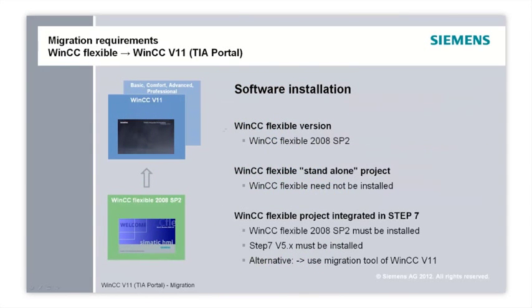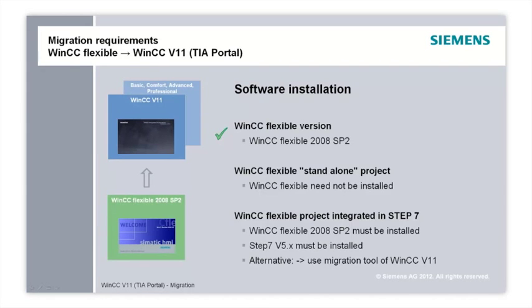Which software requirements apply for the migration? Projects created with WinCC flexible 2008 Service Pack 2 can be migrated to WinCC version 11. When using older or later versions of WinCC flexible, please generate a backup of this configuration, then open this configuration with WinCC flexible 2008 Service Pack 2 or Service Pack 3 and save the configuration as WinCC flexible 2008 Service Pack 2.